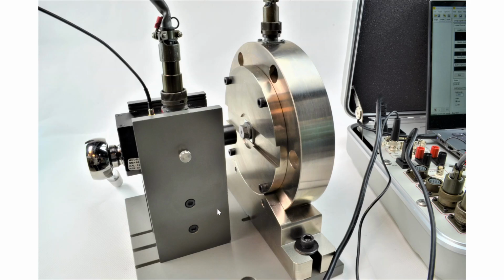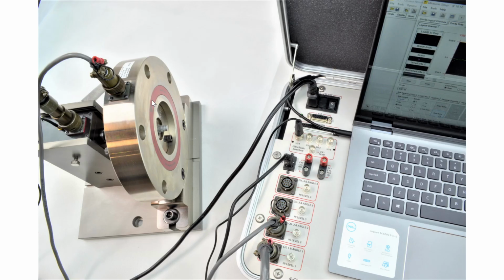This is the setup that I have, the simple setup as I used before. We have a bolt with an ultrasonic sensor glued on top, and I have a fixture which holds the torque angle transducer, which has the ultrasonic pickup option on it. We have a load cell here, but we use this load cell right now just as a joint, not as a load cell. So we will not be collecting data from this connector. We will only be collecting from these two connectors. And this is how we have connected it.